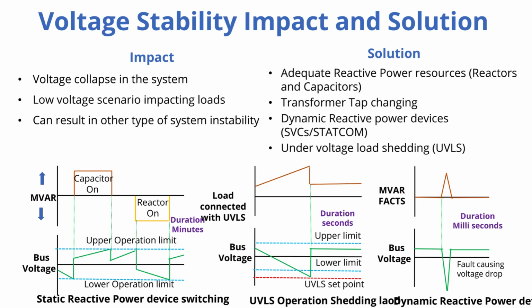What are the main impacts listed for voltage instability? Well, the big one is voltage collapse leading to blackouts. Also, low voltage scenarios impact loads, cause equipment trips, and voltage problems can definitely trigger or worsen other stability issues like transient or frequency problems. It's all interconnected. And the solutions, they seem to mirror the causes. Pretty much. Yeah. The presentation lists having adequate reactive power resources, both static capacitors and reactors and dynamic SVC and STATCOMs, using transformer tap changing to adjust local voltages. And as a last resort, under voltage load shedding, UVLS.